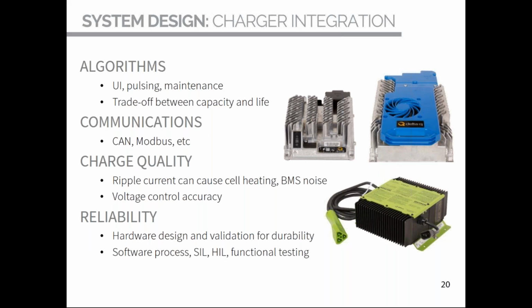Let's talk about why that is. We've already said that lithium batteries will age faster if they're hot. Lithium batteries will also age faster if they spend more time at high voltages and high states of charge. For this reason, you typically don't charge battery packs to their theoretical maximum charge - you don't cram in all the energy that you could, but you limit to a reduced state of charge target. And the art is to carefully select that target. If that target is lower, you'll get less runtime from the battery pack on each cycle, but you'll have a longer expected pack life and warranty because you limit the time spent at high voltage and high states of charge.